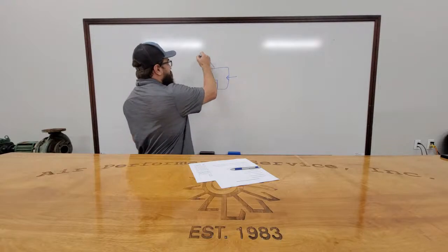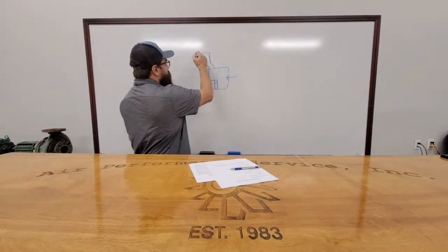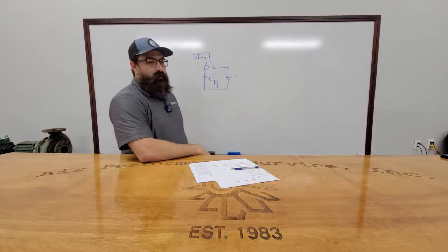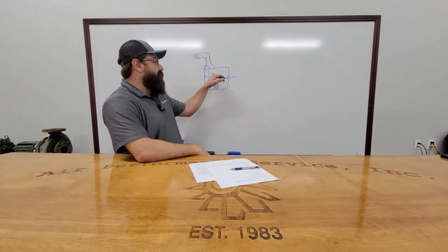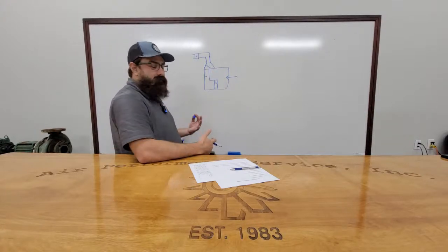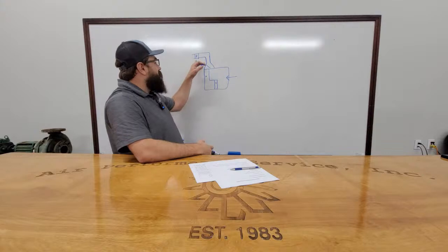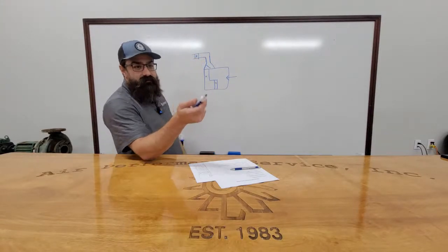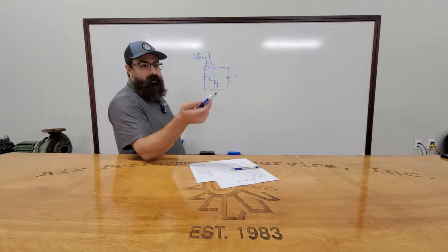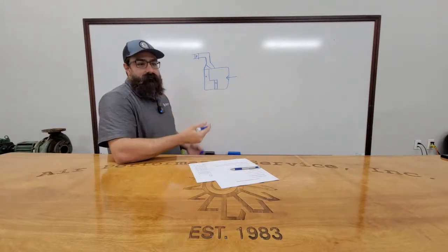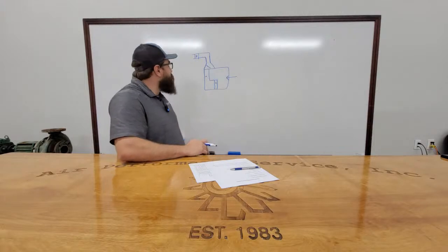In Texas, what we do have would be each zone coming off of this would have a heat kit, either with a hot water valve or an electric heater. And typically they're way, way smaller in load compared to the hot deck that would be on the unit itself. And you would have each one of these based on its own temperature sensor. Kind of like what you were talking about with that unit having all those pin controllers. They basically built the multi-zone is what they were doing.